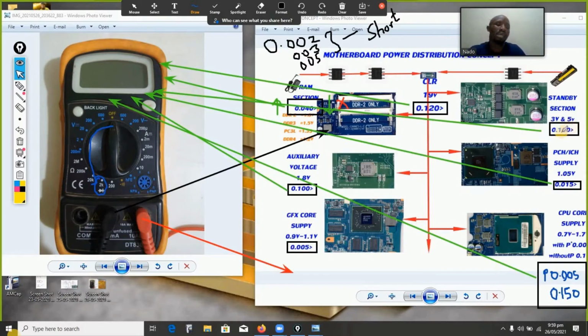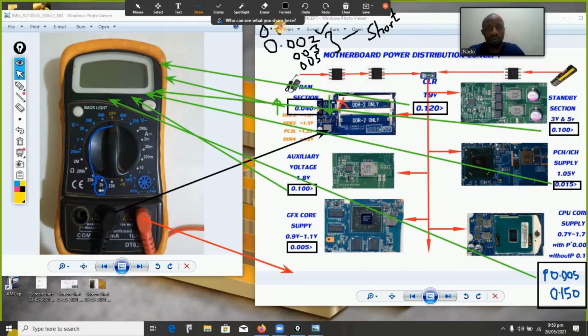Whenever the worst case we can get for this impedance is when we are getting lesser than the expected value here, and the most worst one is when you are having around 0.002, 0.003 for any section. So now if you reverse the voltage, that's what I'm trying to explain here. If you reverse the probe, this is what you are going to get.